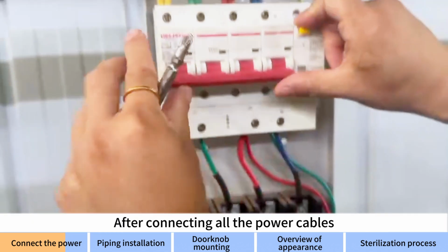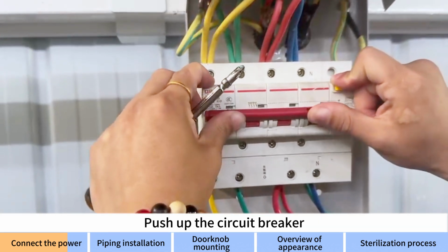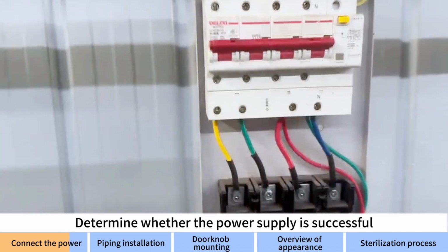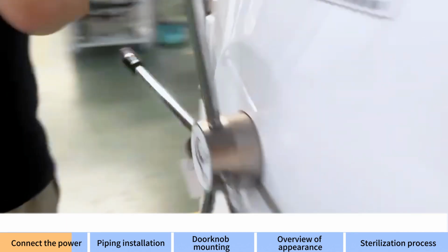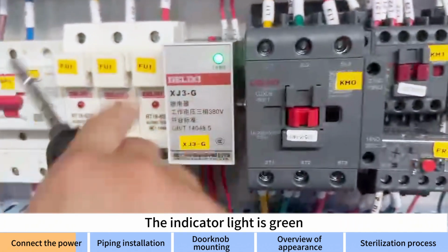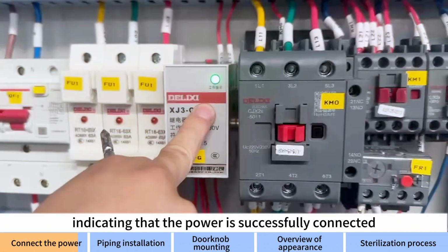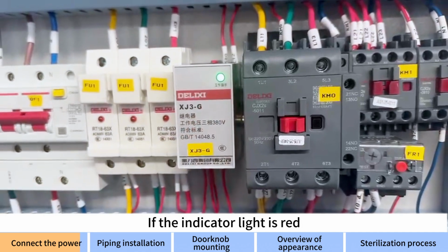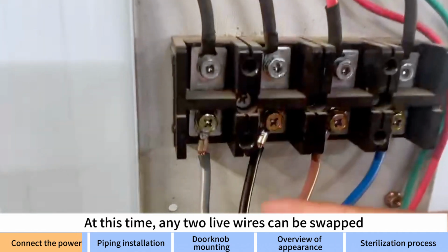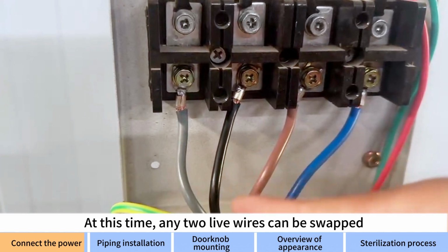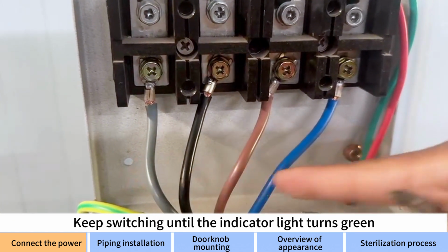After connecting all the power cables, push up the circuit breaker. Determine whether the power supply is successful. Look at the relay indicator light on the side of the device. The indicator light is green, indicating that the power is successfully connected. If the indicator light is red, any 2 live wires can be swapped. Keep switching until the indicator light turns green.